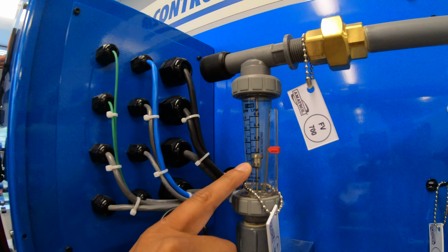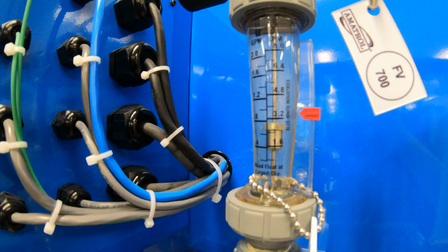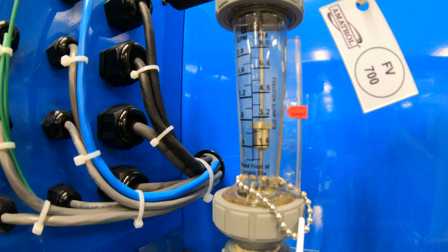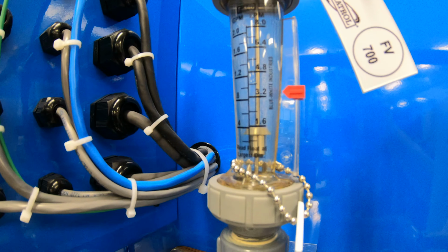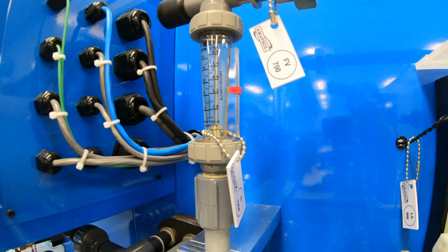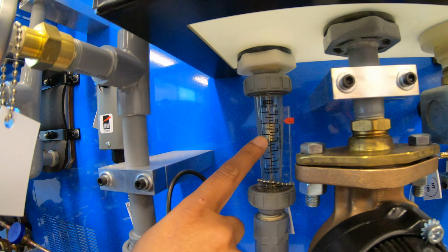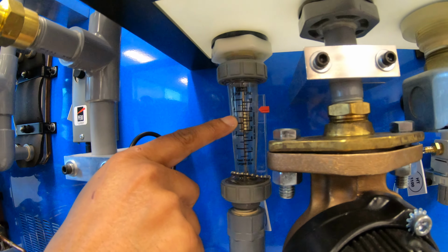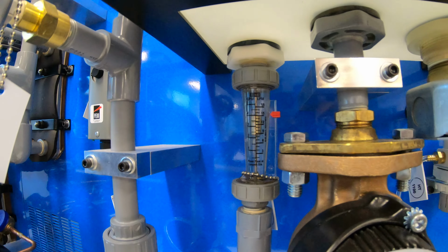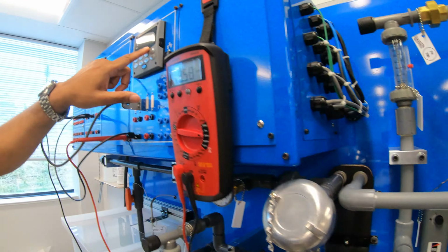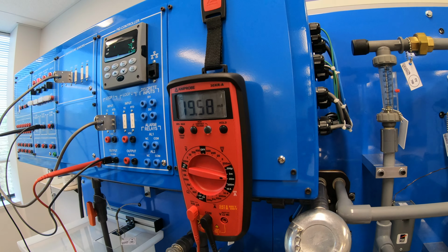When I increase this, you will see that the pressure will drop and the bypass will increase. So I'm going to increase it now to 100, like so. And it'll take just a moment because it takes some time. Right, it totally drops. And as you notice, now it was at 3, now this is at 3.5 going back into the bypass filter, going back into the tank, okay? And you can see in our PID, we're at 97.9% and roughly at 19.5 milliamps of current.